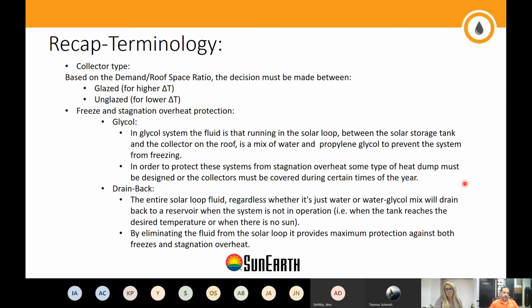You don't have to compensate by adding a large number of coiled heat exchangers into your solar storage tank. Sometimes the space for that is not available to begin with. So that's something that you want to consider. In this design, there are more than a few benefits, because when you think about it, you have a drain back system that provides the maximum protection against both freezes and stagnation overheat.